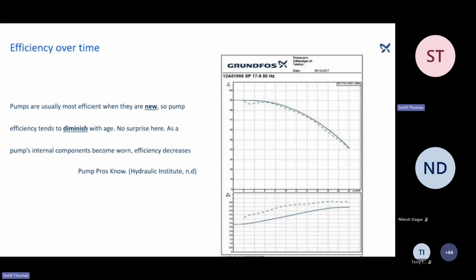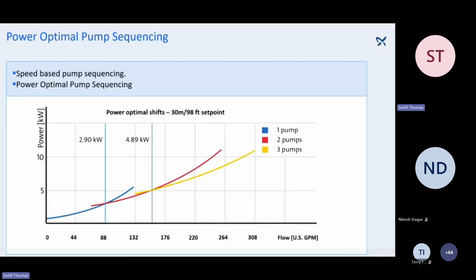As you know, efficiency over time is definitely going to diminish, because these are all mechanical components. You will have wear and tear over a period of time, let's suppose 10 years, and the hydraulic efficiency is definitely going to come down after a point of time. So in order to cater to that, we have what is called power optimal pump sequencing, which looks into the current situation of the system. It identifies which would be the best scenario in terms of power demand, and stages the pumps accordingly based on power. This is a feature we have inbuilt in our systems, to make sure that the efficiency is not compromised, and at the same time it's running at much less energy consumption as well.